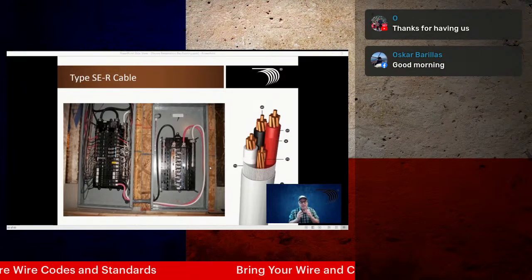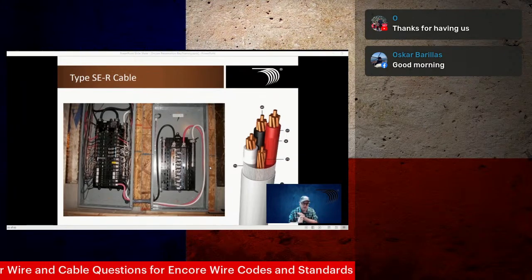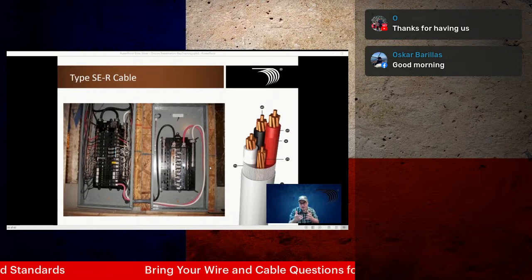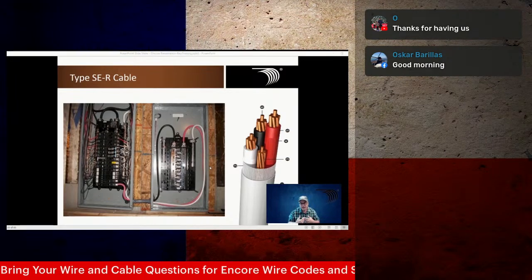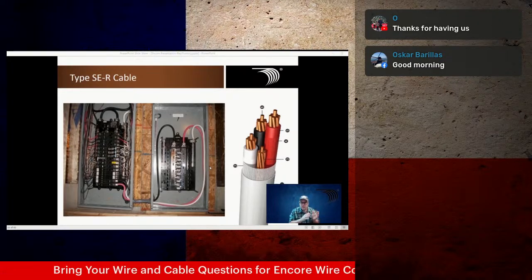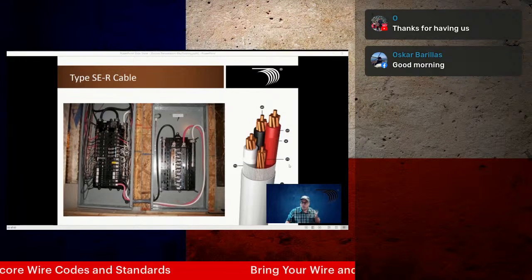Now, the thing about the SER is that it can't go below grade. It's an above ground product. So this is where the hybrid comes in. The hybrid takes an SER and turns it into a tray cable, which is rated for direct burial. So that's the beautiful thing about that hybrid product that we offer. But we do make the SEU and the SER, again, as you see here, available in copper or aluminum.